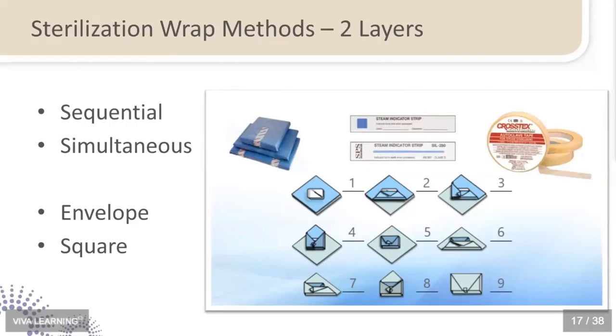When you are doing 2 layers of wrap, you have choices. You can do it sequentially, which you can think of as a package in a package. You're going to wrap the cassette completely the first time, then you're going to lay that wrapped cassette down on a new piece of wrap, and you're going to wrap it again, a package within a package. The other choice that we have, some manufacturers offer a bonded wrap, which means that it's 2 pieces of wrap, but they're ultrasonically welded or bonded on either 2 or 4 of the edges. So when you pick up that wrap, you're already picking up 2 at the same time. With that, obviously, you're going to be doing simultaneous wrapping because it's bonded together, and you're going to only do 1 wrap procedure. So obviously you save time when you're working with a bonded wrap and simultaneous.